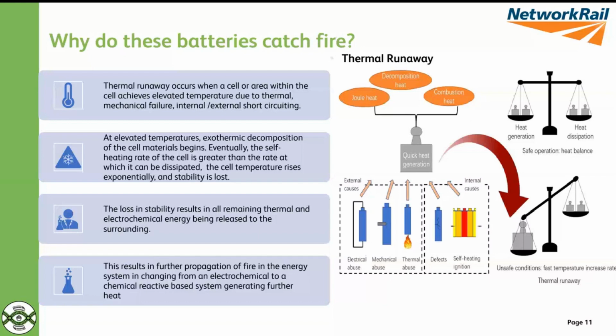As it raises temperature, you get an exothermic decomposition of the cell materials, which increases the rate of self-heating. Then you reach a stage where the amount of heat being generated is more than the rate of heat that can be dissipated from the battery, resulting in a loss of stability of the remaining energy within the battery. That leads to further propagation, where you get a release of energy from the battery in a fire. I've tried to illustrate that graphically in terms of the scales of heating: self-heat being generated that you can't dissipate quickly enough leads to a rise in overall temperature, which compounds the problem.